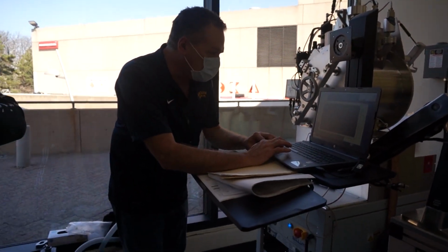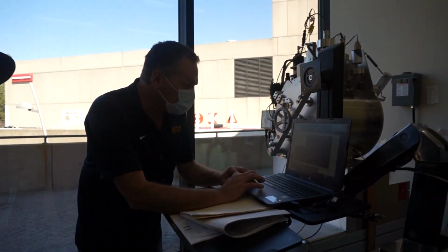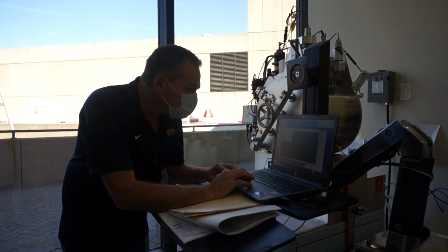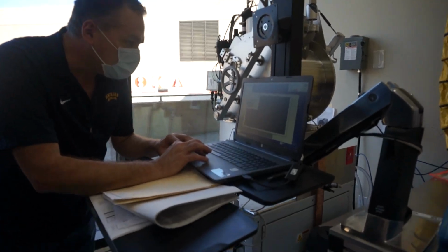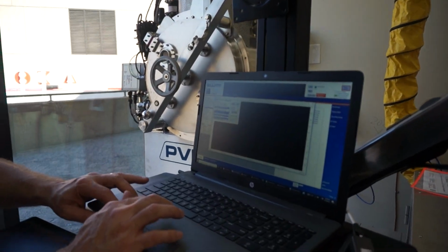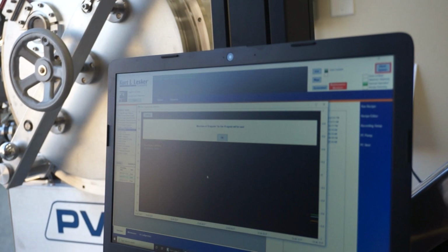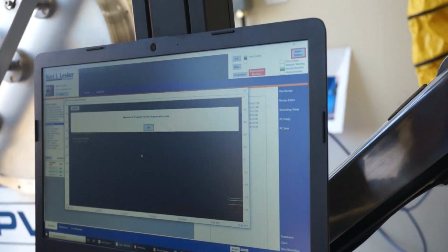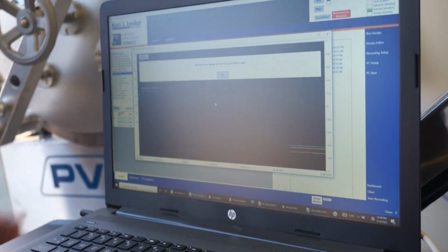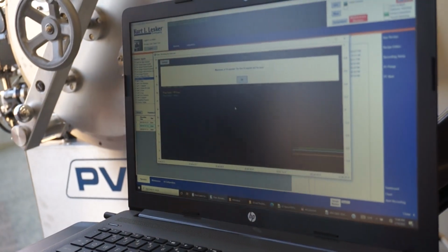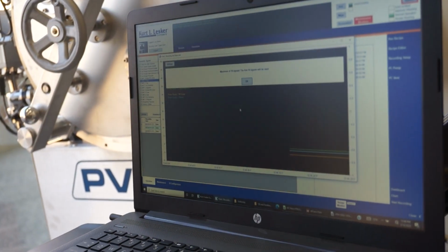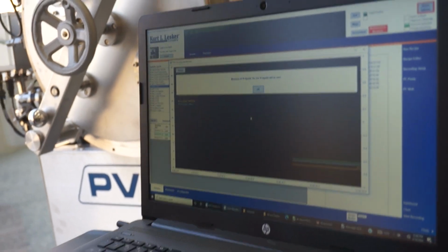So once again, the chart, I can go to the settings here, and I'm just going to go to save sets. If I click this, it's going to show the first 10, maximum 10 signals, first type thing to be recorded. So we use this. Let's say we want to plot time over power, whatever. You can kind of see it. You can save this chart. There's lots of flexibility in here.